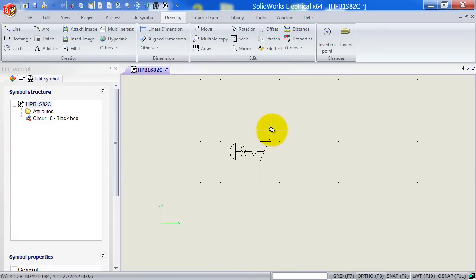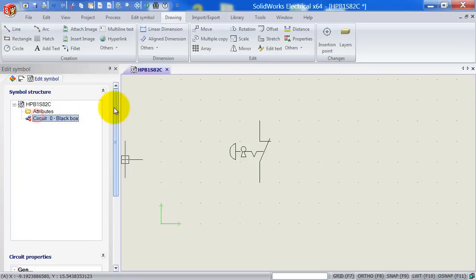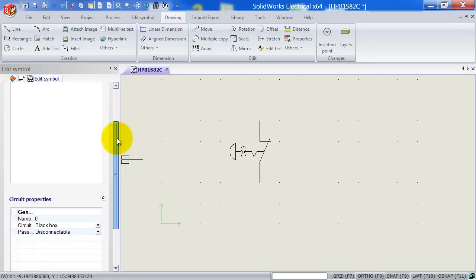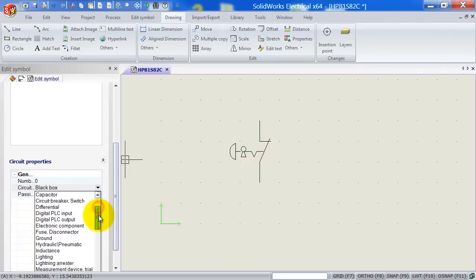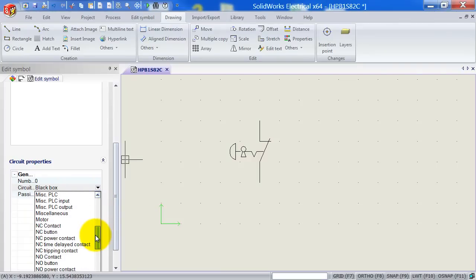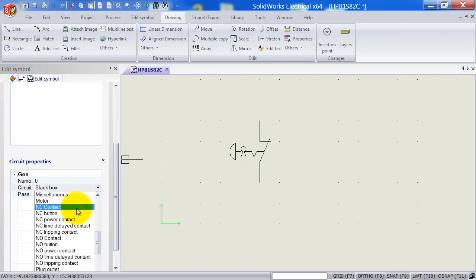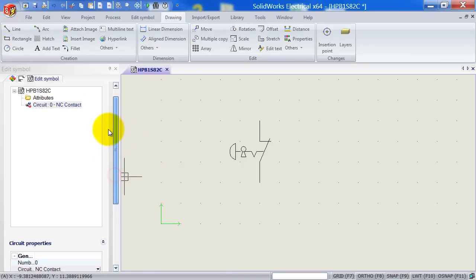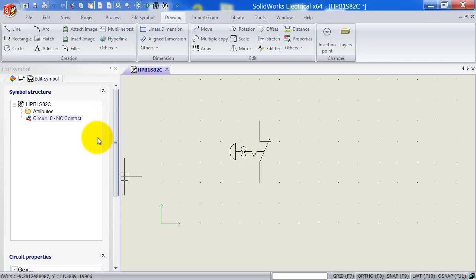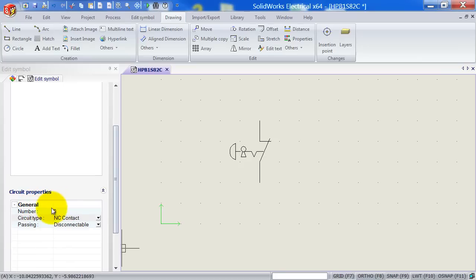What we're going to do now is we can see there is still a circuit defined here, circuit zero, so that's great, but it's associated with a black box. Now we don't want that to be associated with a black box because it's going to be a switch. So if I drop this down, there is a normally closed contact. That's the one we're going to use. And it's disconnectable. That's good. So again, as I said in my previous videos, you set the circuit here so that SOLIDWORKS Electrical will do a double check for us when we associate that to a part.